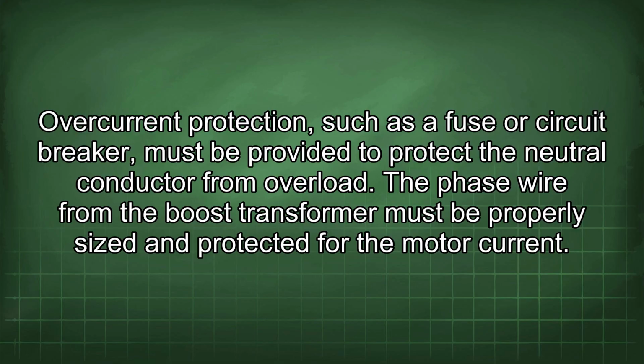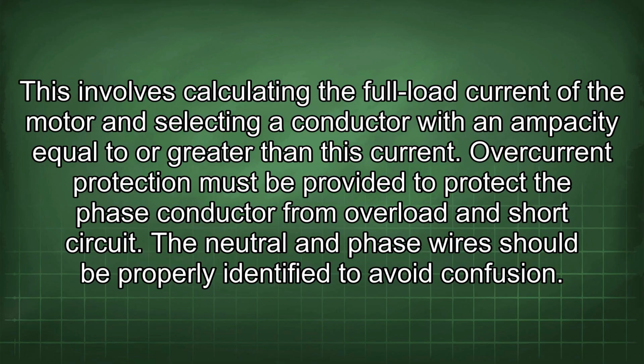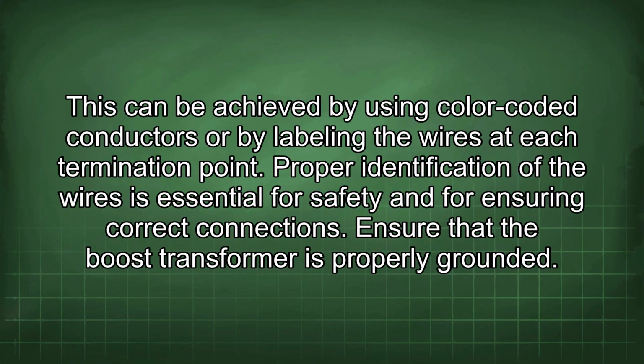The phase wire from the boost transformer must be properly sized and protected for the motor current. This involves calculating the full load current of the motor and selecting a conductor with an ampacity equal to or greater than this current. Overcurrent protection must be provided to protect the phase conductor from overload and short circuit. The neutral and phase wires should be properly identified to avoid confusion. This can be achieved by using color-coded conductors or by labeling the wires at each termination point. Proper identification of the wires is essential for safety and for ensuring correct connections.